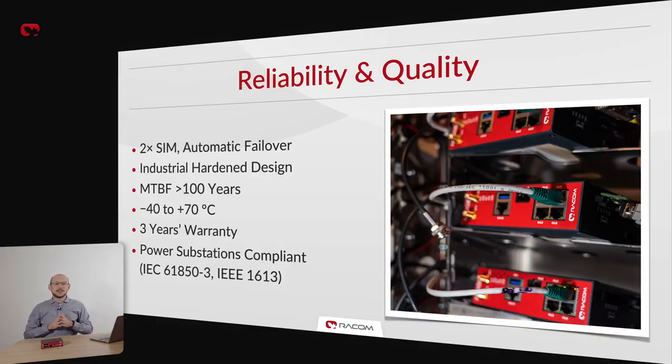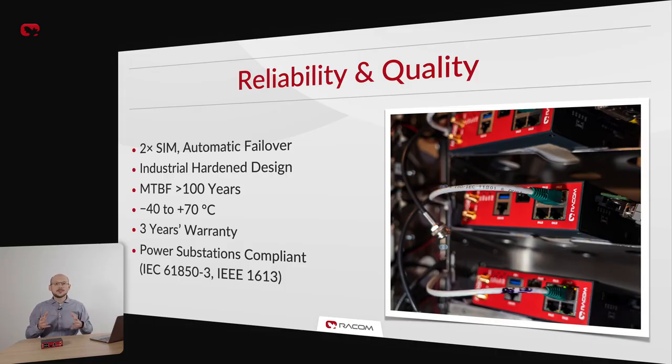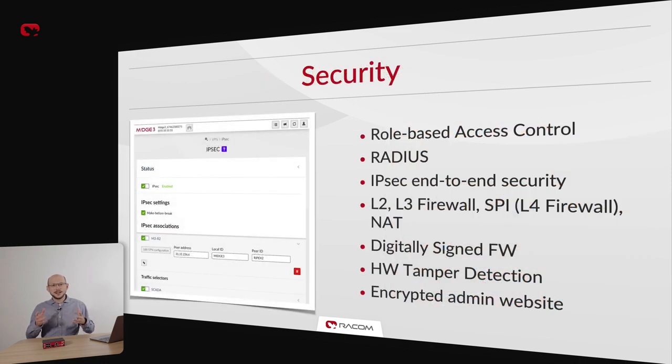Reliability is critical in our business. That is why we are happy to say M!DGE3 can boast an MTBF of over 100 years, thanks to our meticulous manufacturing and QA processes and durable construction. As a mark of the confidence we have in our products, we offer a full 3-year warranty on all RACOM devices as standard. M!DGE3 features two SIM card slots with automatic failover and can withstand operating temperatures from minus 40 to plus 70 degrees Celsius. M!DGE3 is the first cellular router in our history to offer full IEC 61850-3 electrical substation compliance.